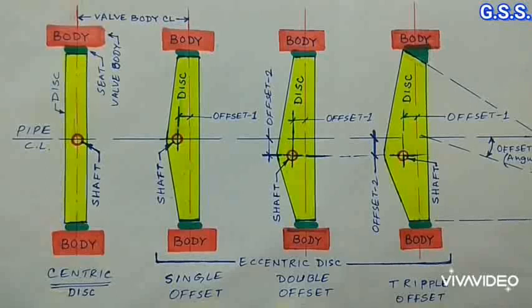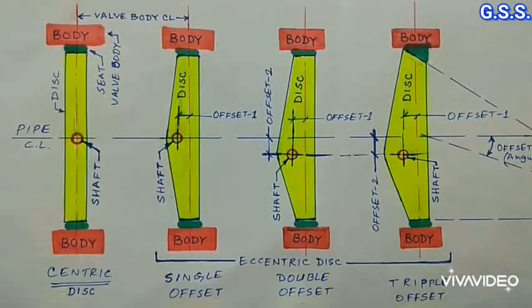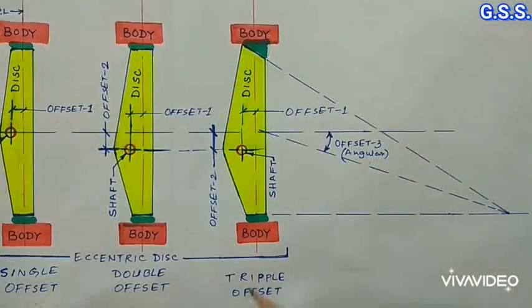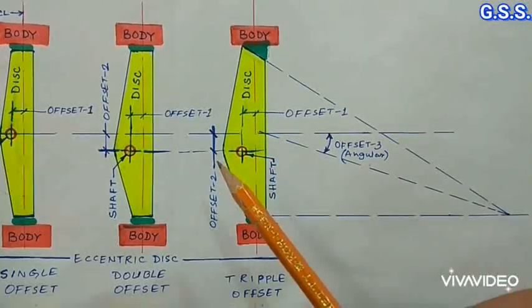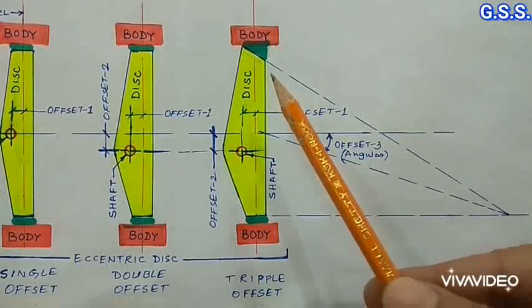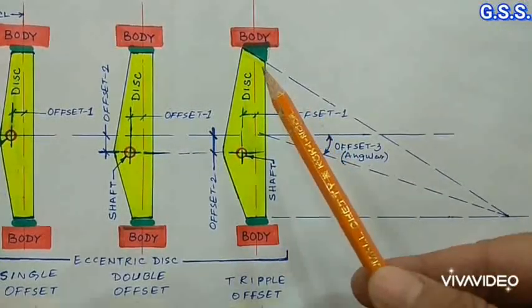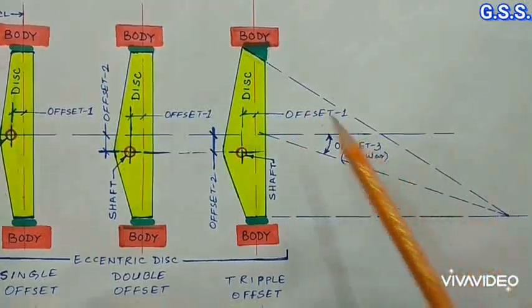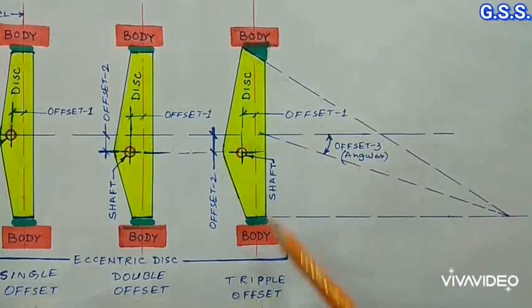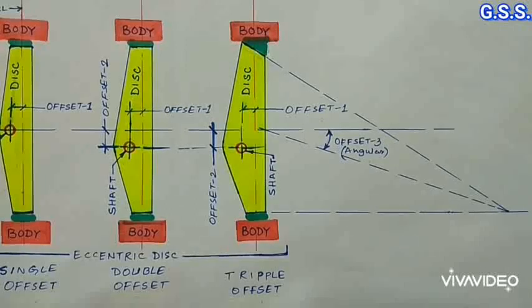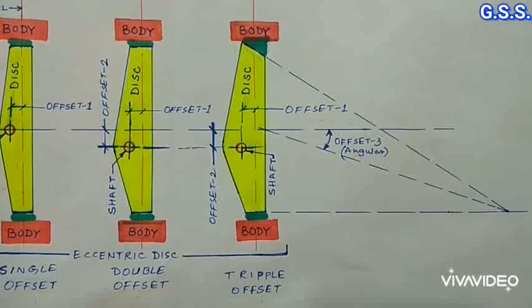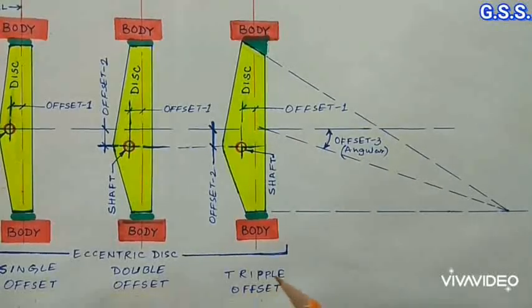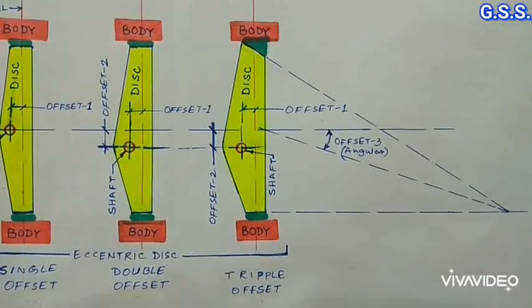In double offset arrangement, there will be less friction on seat and valve's life will be more. In triple offset butterfly valve, three offsets are there. Two offsets are same as double offset butterfly valve. But additionally, third offset is conical shape disc, which matches with conical shape metal seat. In this arrangement, there will not be any friction or rubbing on the seat and makes the valve bubble tight shutoff in high pressure and in high temperature application. Also, valve will have longer life. Double offset and triple offset butterfly valves are called high performance butterfly valves.